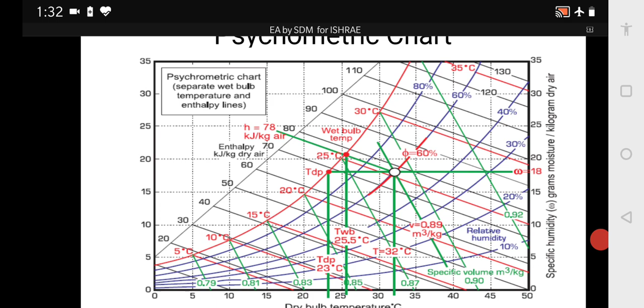And you can see the psychrometric chart. For 2 minutes I will explain this psychrometric chart developed by Carrier. This is for 1 atmospheric pressure. You can see on the x-axis the dry bulb temperatures, and on the y-axis 0 to 35, that is the grams of water vapor per kg of dry air. This is the specific humidity. And the red curved line is the saturation line, the 100% saturation line.